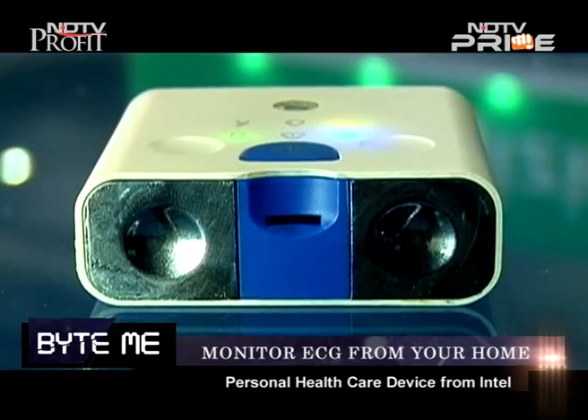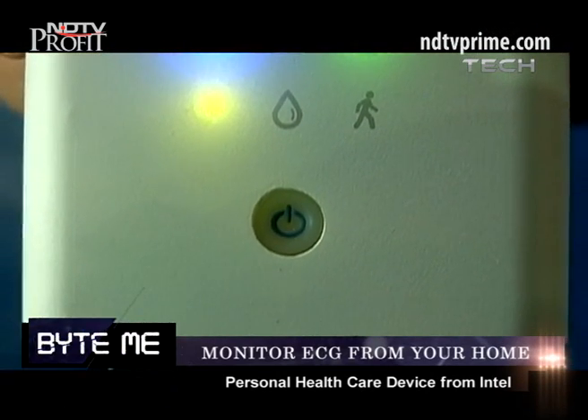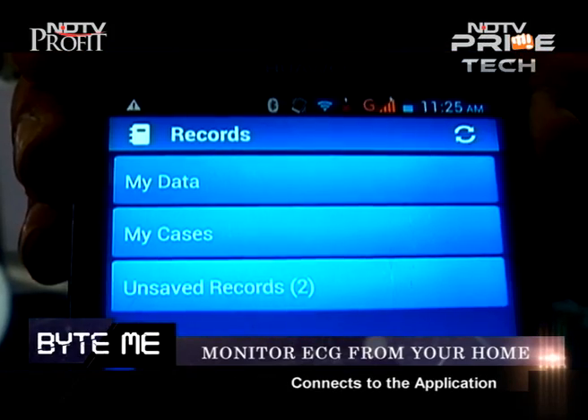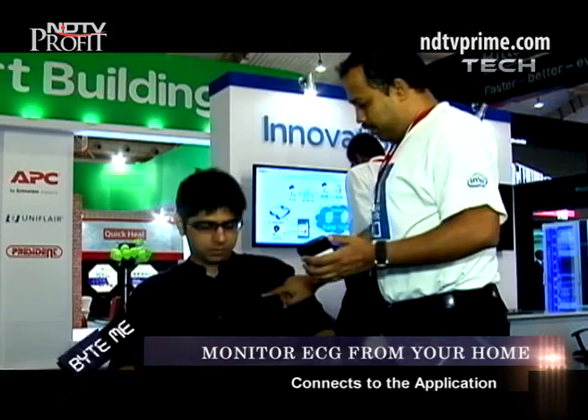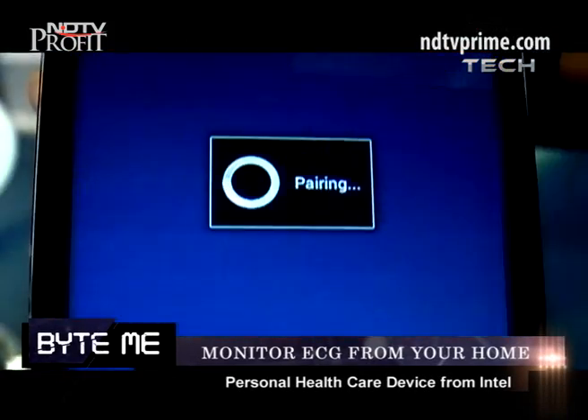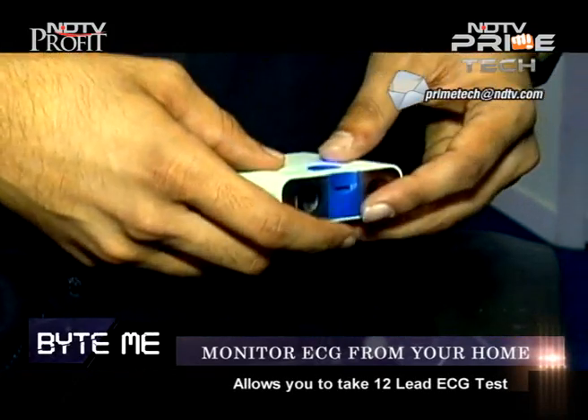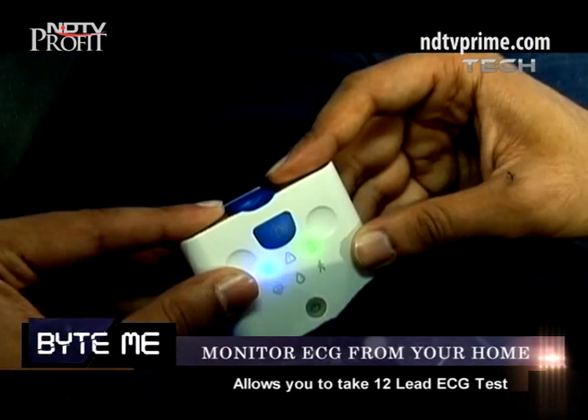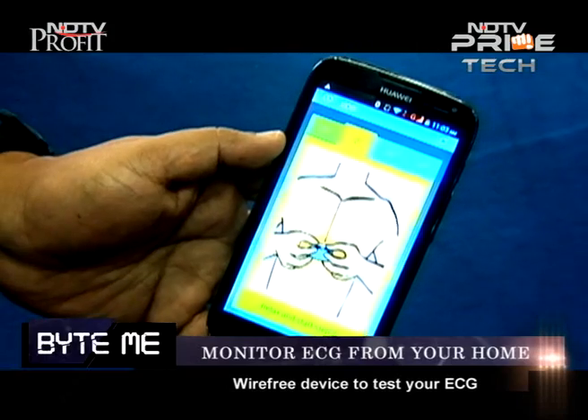There are 100 million people in India who are either affected by diabetes and cardio diseases and we are generally labeled as lifestyle disease capital of the world. So we are coming out with this reference design which is a personal healthcare reference design — an end-to-end solution consisting of this device, mobile applications, and also the cloud backend through which a patient at home can measure several things. The unique part of this device, used along with an application on a mobile phone, is that it allows you to take a 12-lead ECG at the convenience of your home and you don't need to have wires. Typically all the ECG devices have these leads that are hanging out. So you touch this device at several points in your body as instructed by the mobile application and measure your 12-lead ECG.